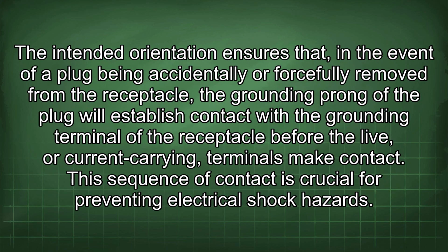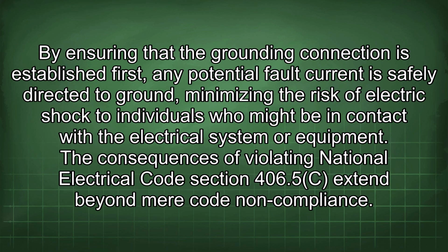The intended orientation ensures that, in the event of a plug being accidentally or forcefully removed from the receptacle, the grounding prong of the plug will establish contact with the grounding terminal of the receptacle before the live, or current-carrying, terminals make contact. This sequence of contact is crucial for preventing electrical shock hazards. By ensuring that the grounding connection is established first, any potential fault current is safely directed to ground, minimizing the risk of electric shock to individuals who might be in contact with the electrical system or equipment.